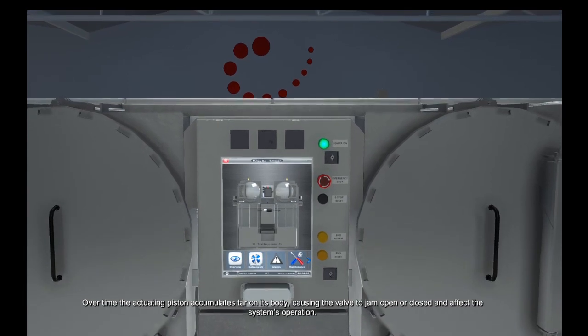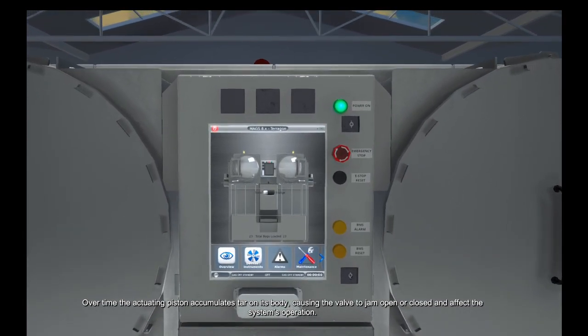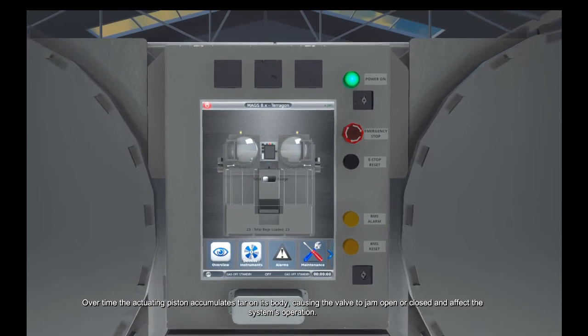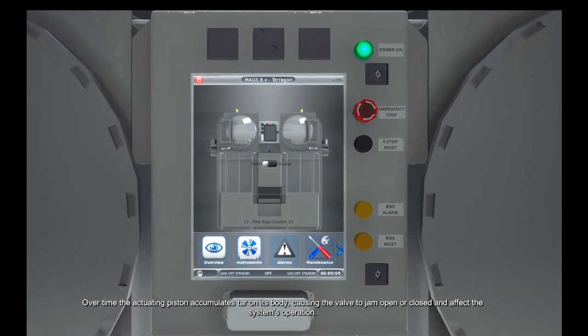Over time, the actuating piston accumulates tar on its body, causing the valve to jam open or closed and affect the system's operation.